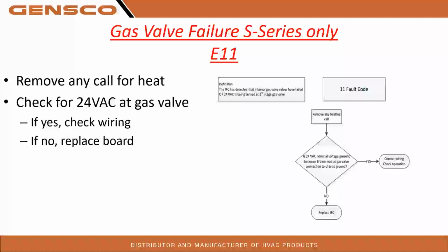So gas valve failure, this is going to be an S-series furnace only. So we're going to remove the call for heat. We're going to check for 24 volts at the gas valve. If yes, check wiring. If no, replace the control board. So yet again, very nice flow chart here, right? So remove call for heating. We're actually asking you to go to the brown lead at the gas valve to the chassis ground. And no, yes, right? If yes, check wiring and correct operation. If no, replace the control board.